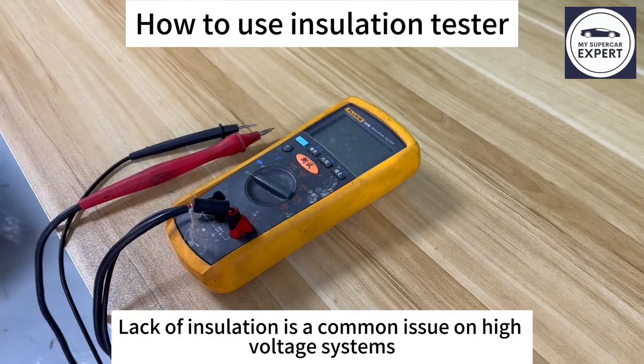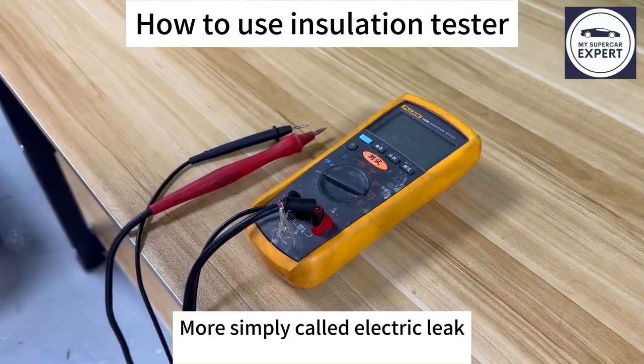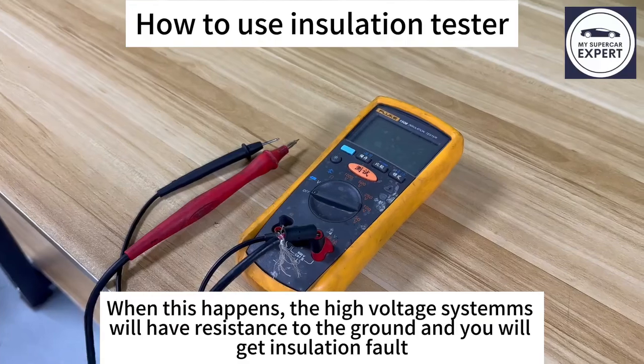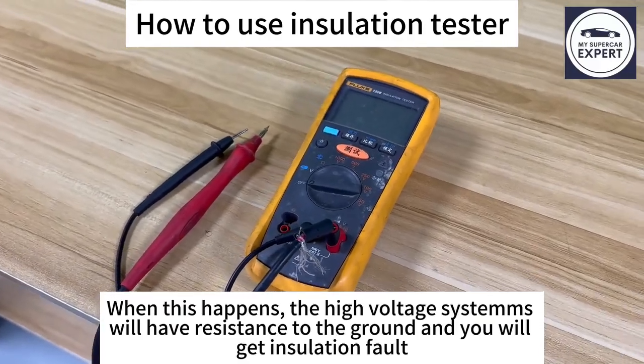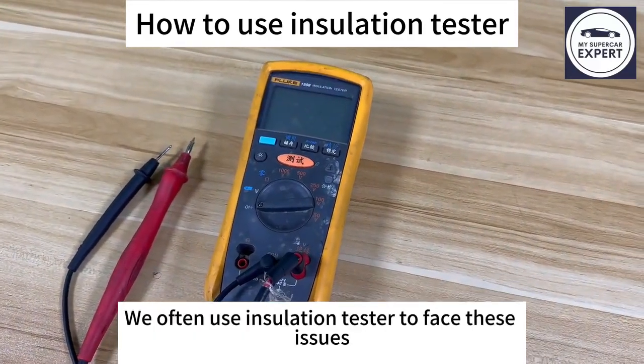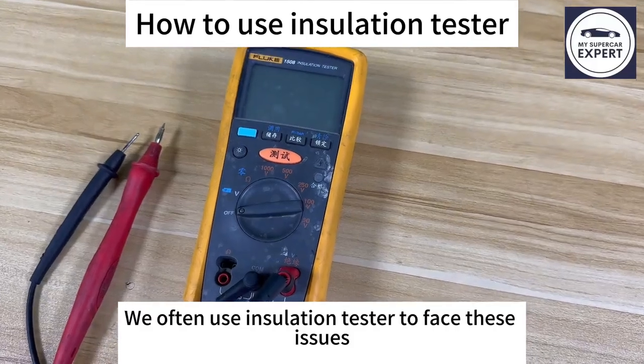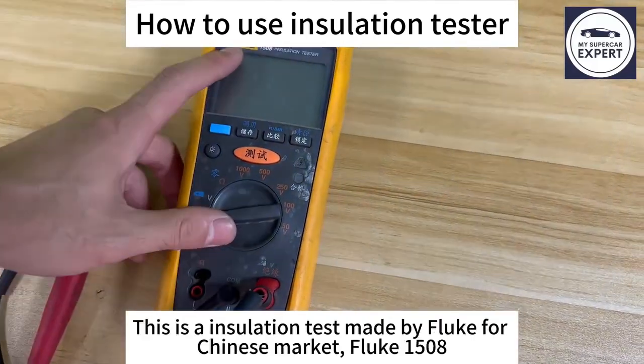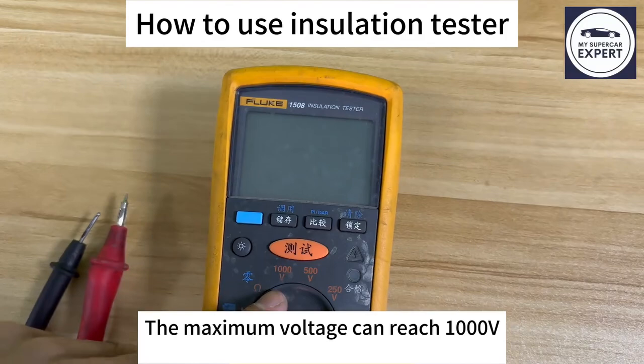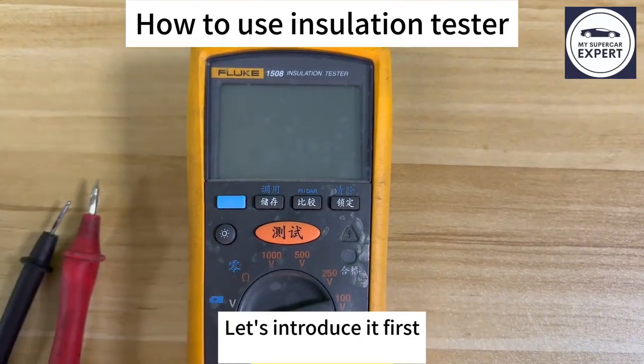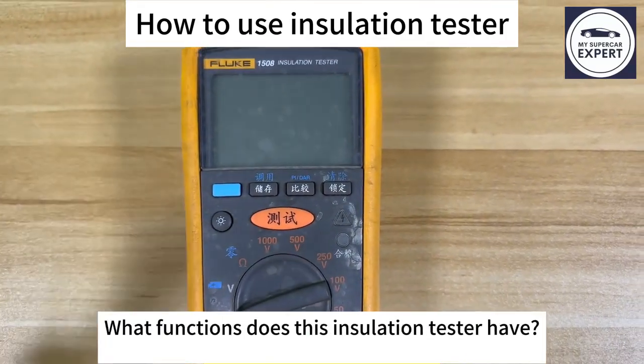Lack of insulation is a common issue on high-voltage systems, more simply called electric leak. When this happens, the high-voltage systems will have resistance to the ground, and you will get an insulation fault. We often use an insulation tester to face these issues. This is an insulation tester made by Fluke for the Chinese market, the Fluke 1508. Maximum voltage can reach 1000 volts. Let's introduce it first. What functions does this insulation tester have?